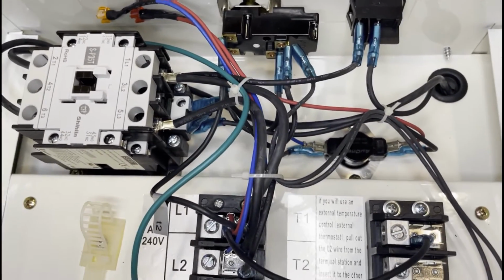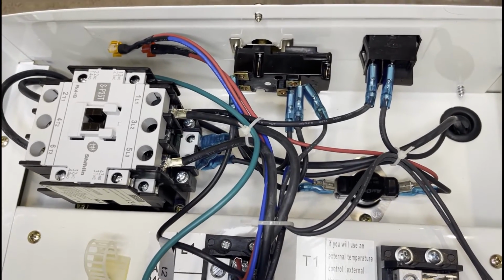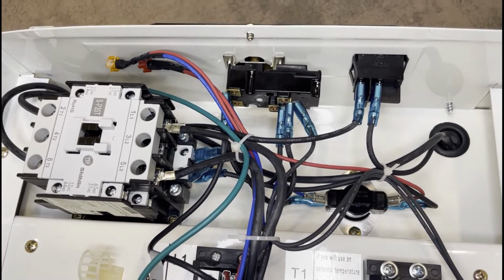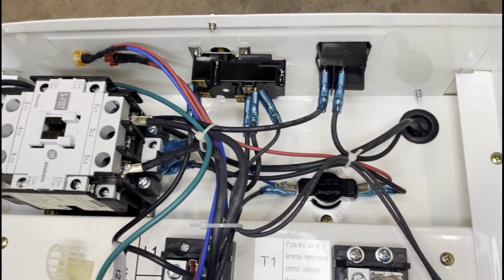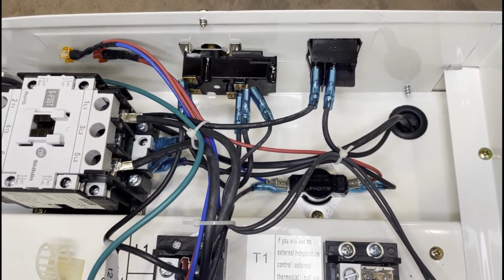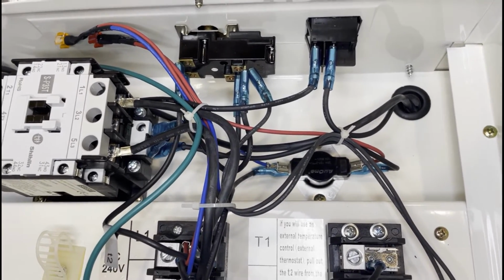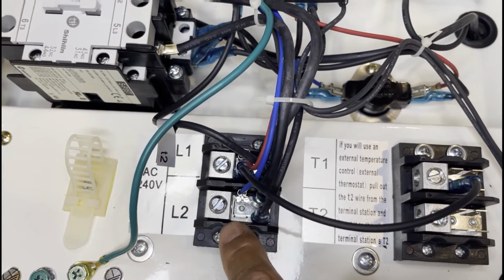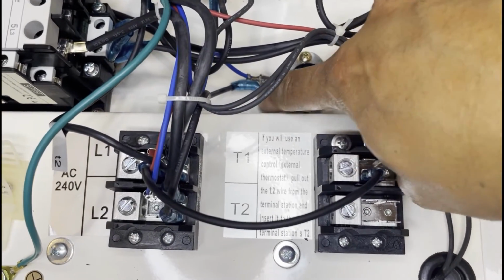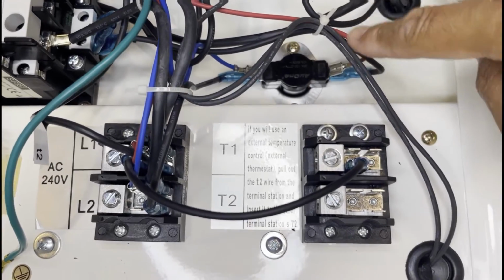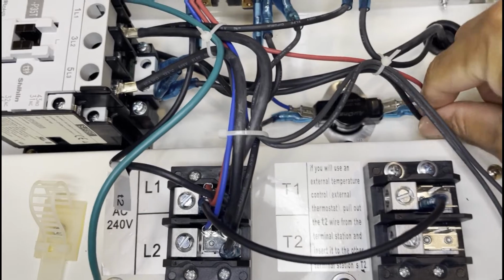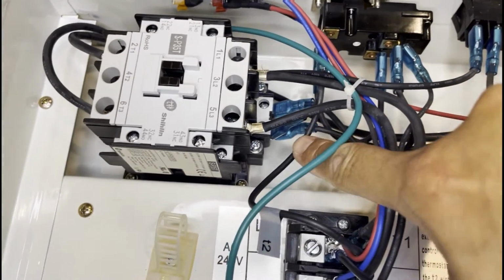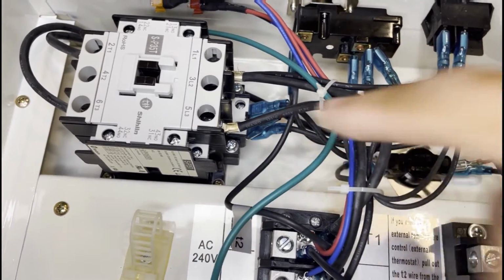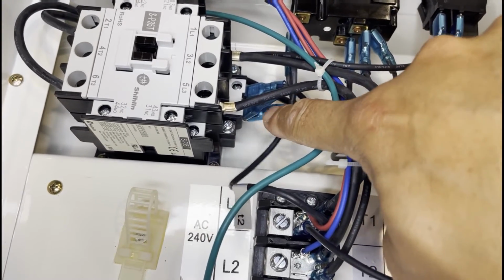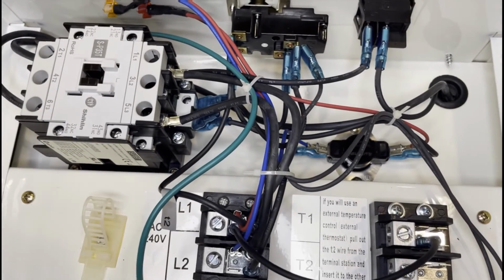Okay, now this also has this limit switch. Okay, it basically controls the fan on and off. This control also provides a safety limit that turns off the heating element if the temperature of the heater gets too high or too hot. So I'm not going to mess with that. We're just going to leave that alone. On the other side of this terminal, you got L2 right here connected to our limit switch. Okay, and then on the other side of this limit switch is connected to, I think it's right here, that goes to our contactor. This one has another piggyback connector, and then the other connector on the other side goes to our fan motor. So basically that completes the electrical circuit.